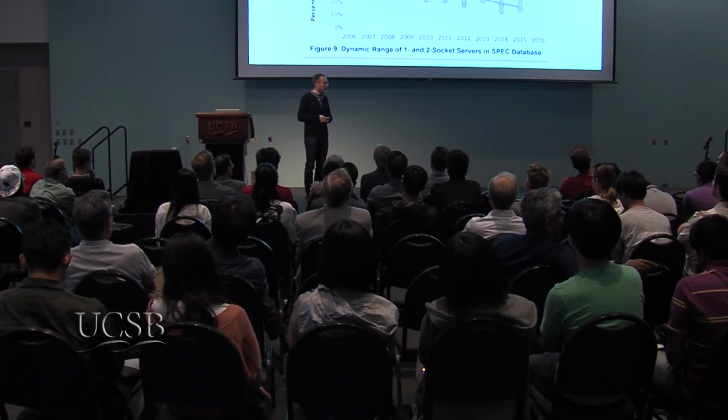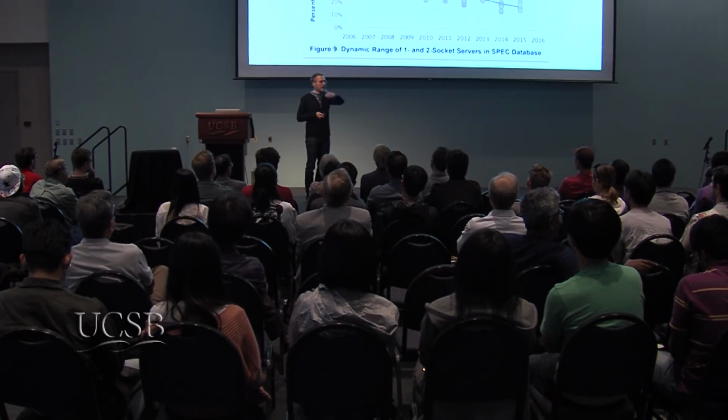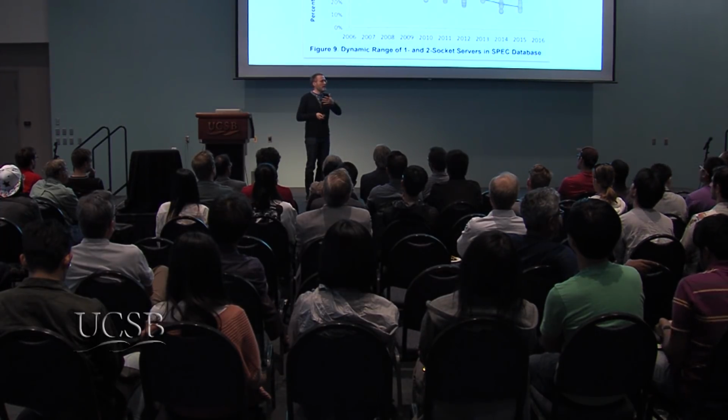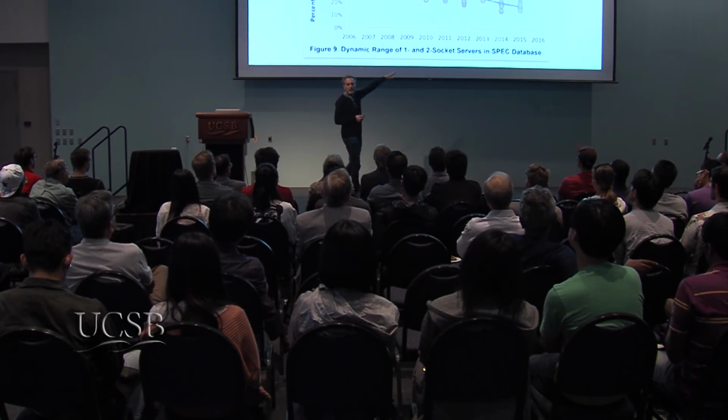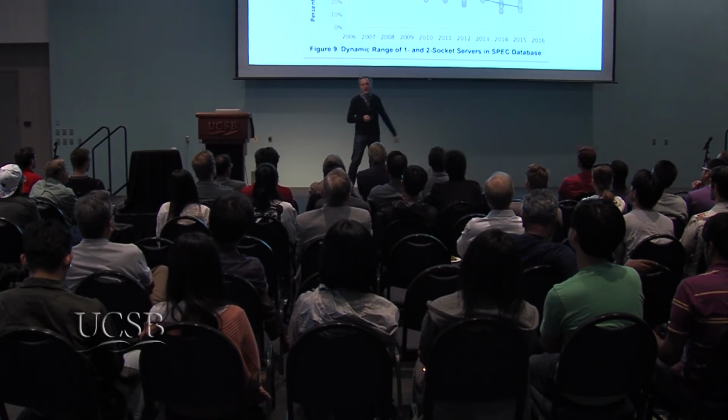And clock gating that I mentioned before is actually one of the ways how this works, right? And frequency scaling. So that's very, very useful because in a typical data center, even in a well-run data center, the average utilization is more around 50, 60%, not 100%. Makes sense, at peak day versus 3 a.m., the load is just not the same. In a typical enterprise data center, by the way, the average utilization is more like between 10 and 15%, so it's actually very bad, right? And that's where this matters even more for energy usage.